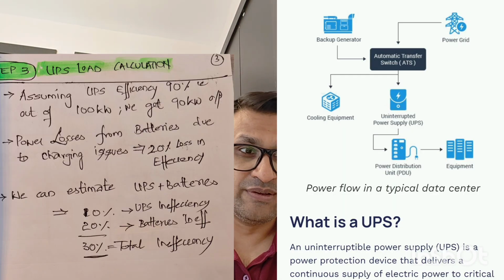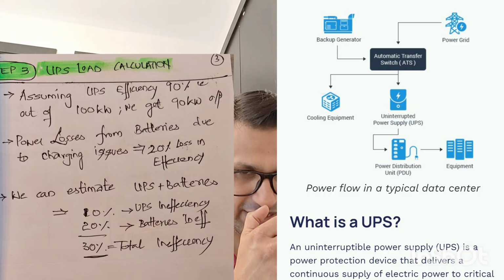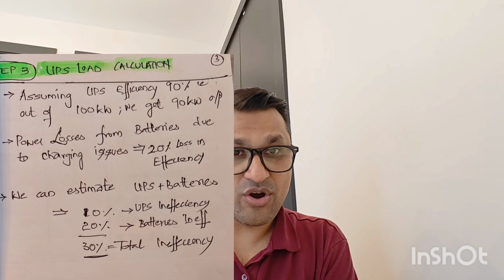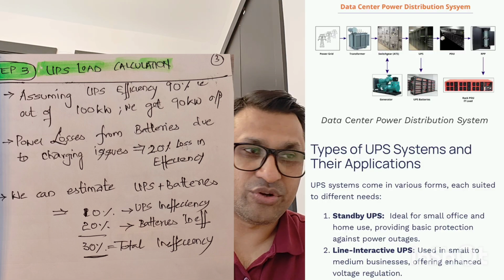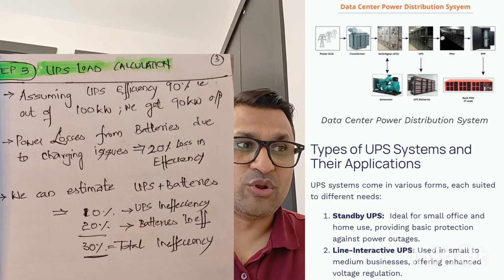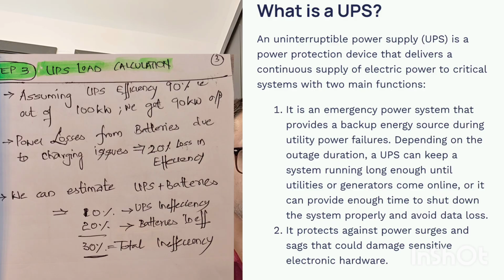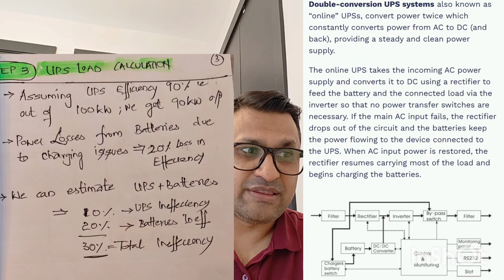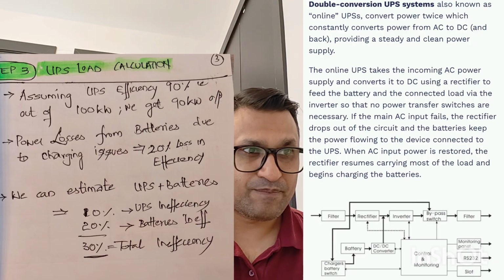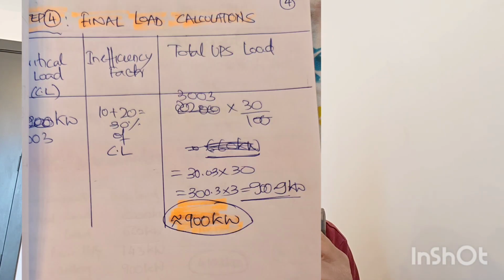And now step 3, UPS load calculation. If you're assuming your UPS is 90% efficient, that is, for 100 watts, you're getting 90; for 100 kilowatt, you're getting 90 kilowatt output. Power losses from batteries due to charging issues and other inefficiencies, let's consider 20%. We can estimate UPS and batteries. That's 10 plus 20%, which is going to be 30% total inefficiency. 10% inefficiency due to the UPS, and then 20% for the batteries. So total inefficiency is 30%.